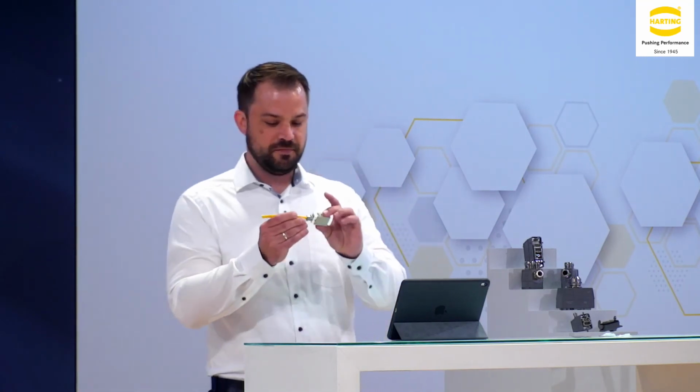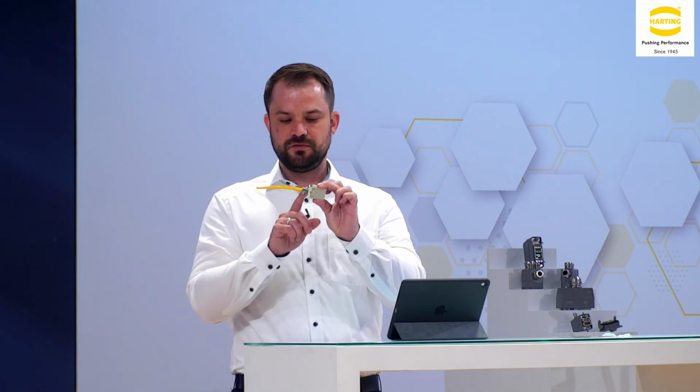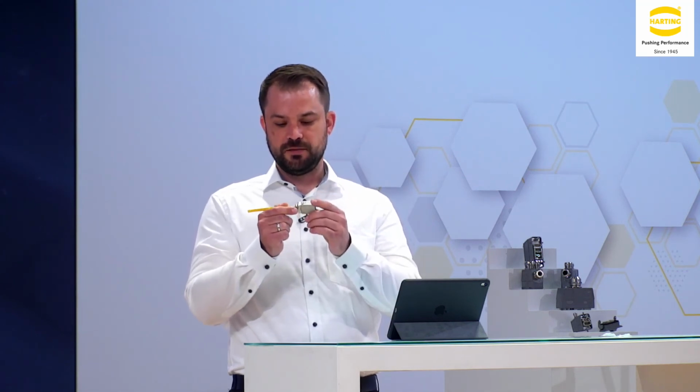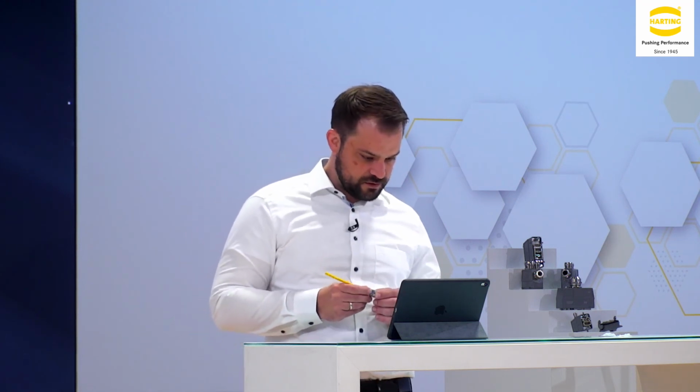As I said, the shielding mechanism is realized with these metal clamps in the rear of the metal modules. And those metal clamps, of course, have a range of cable diameters that can be implemented. And this range was asked what this range is, and it goes from 4 millimeters to 14 millimeters.